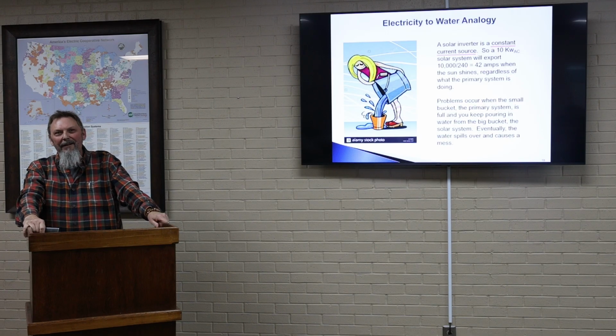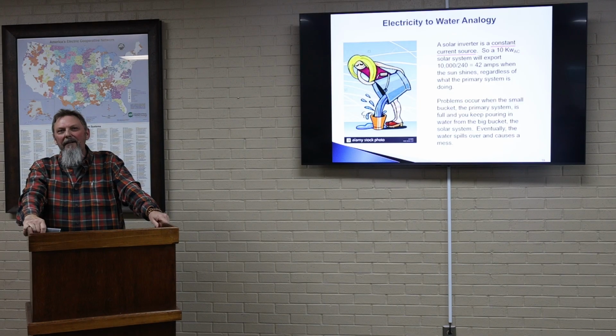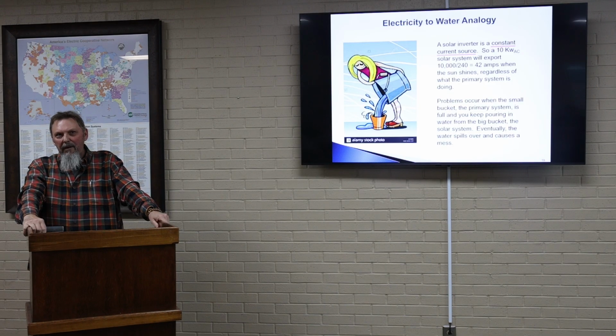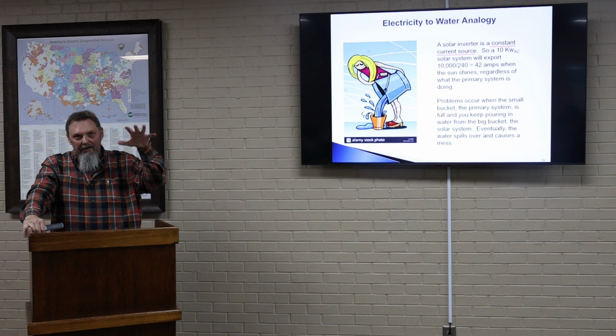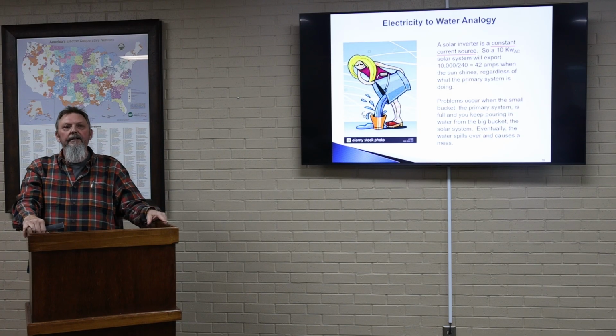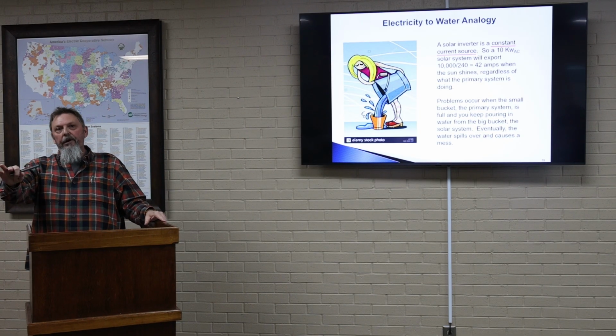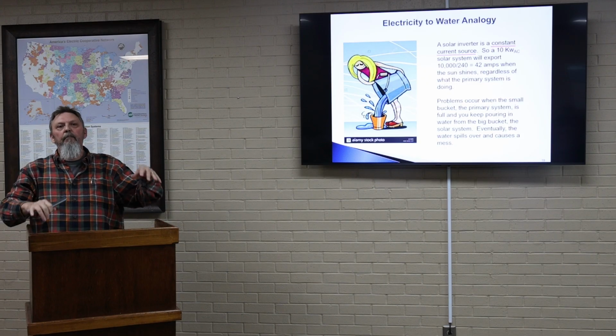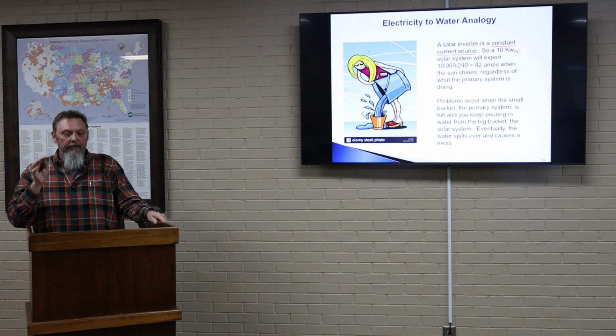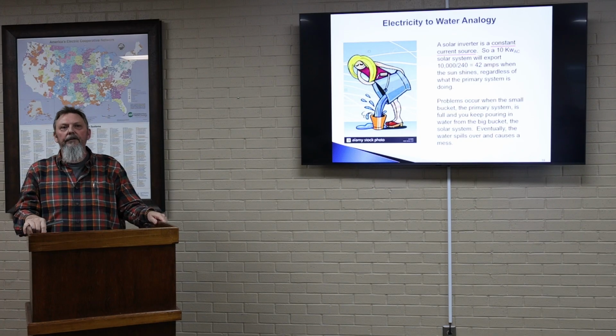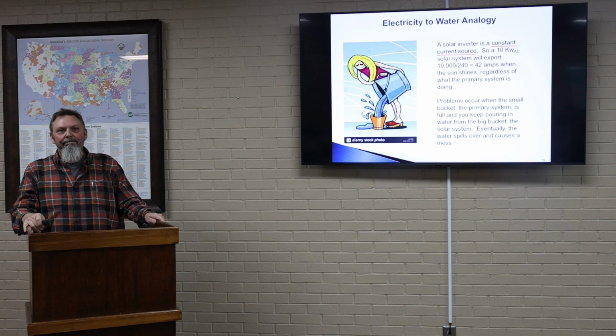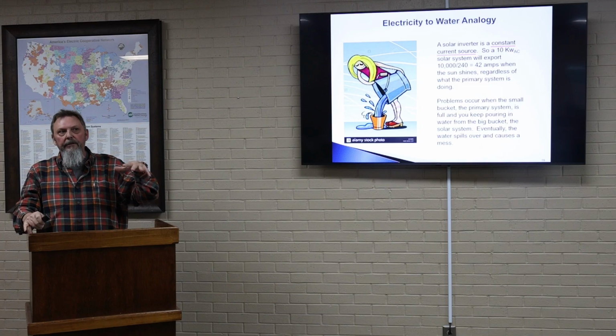Yes, sir, Steve — if there's 13, your house is putting out 13, you're only putting 10 back out onto Ozark Electric, isn't the other 3 just lost? Well, it throttles the system down — it doesn't generate the other 3, it just generates the 10. That's how it works. The inverter throttles down and only does 10 instead of 13. Then if you start using it again, it'll throttle back up and pump it to you. But the way we meter it, it can't go back out onto the grid. Right, so the inverter takes care of that by adjusting its output.